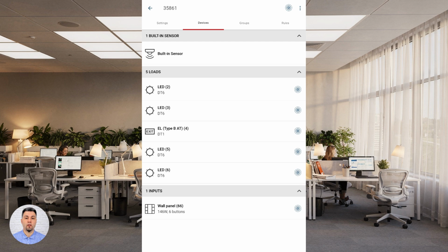Sub-devices cannot be grouped. Although they may have different light levels for various features, they always share the same state machine. For example, moving to occupied, transition, and minimum together. Additionally, PIR triggers from any sensor are always treated as a control input for all sub-devices.